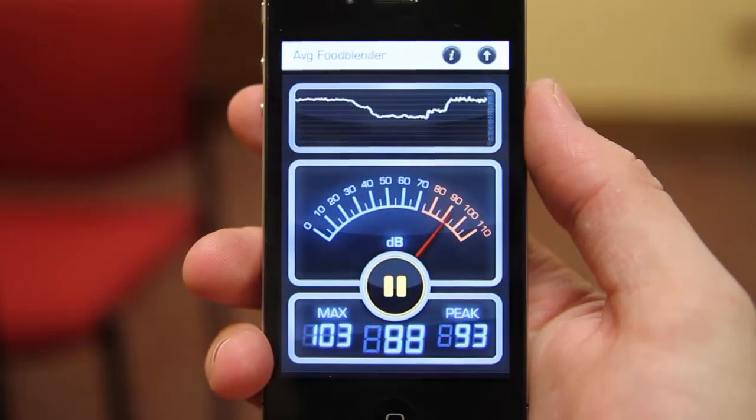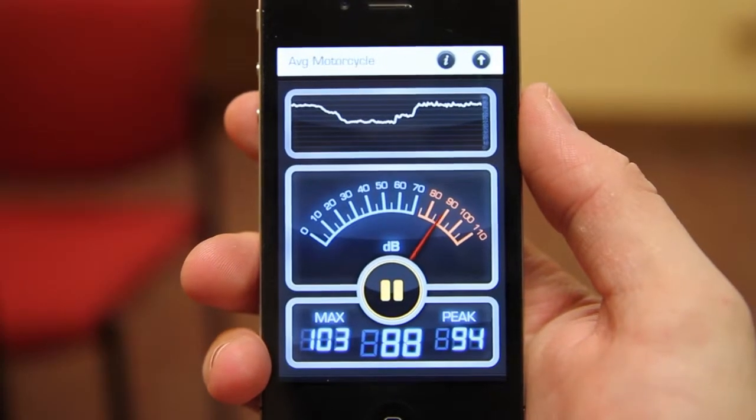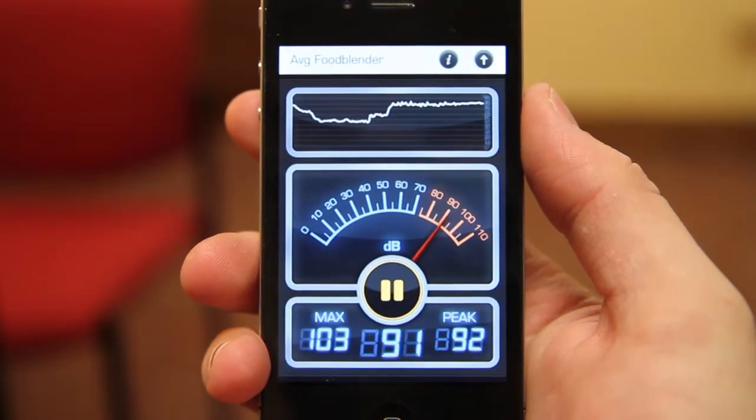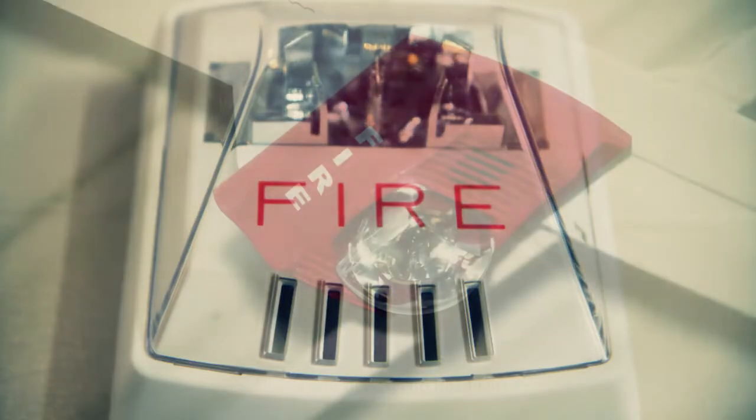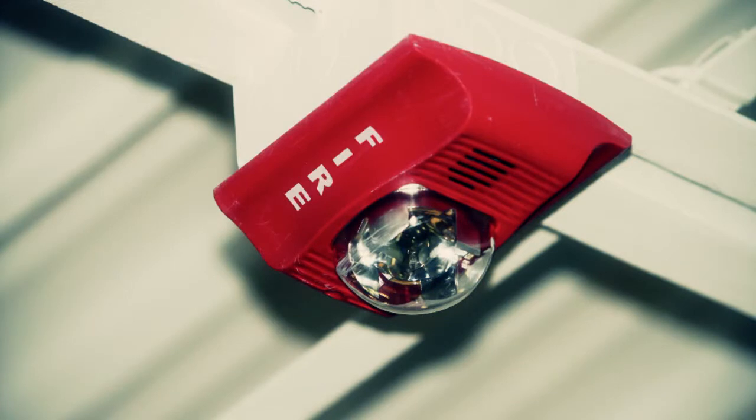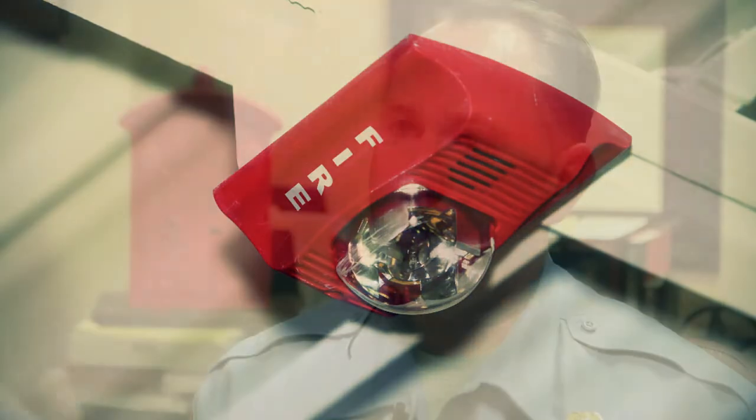Those alarm devices have to ring at a minimum of 85 decibels, so 85 to 110 is what they're typically set at. And when you walk out into a corridor of a large office building, you should see audio-visual devices in the corridors, either on the walls or mounted to the ceiling. And they should have noise and a lot of light. It's to alert you, to help you get out and remind you, hey, it's time to go.